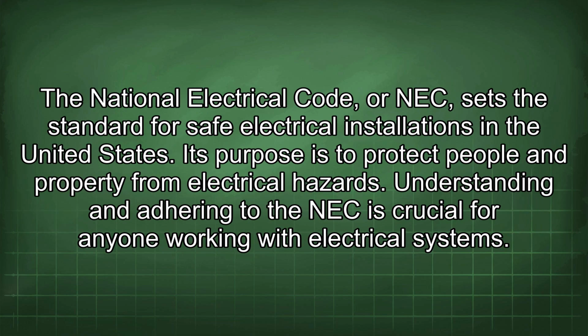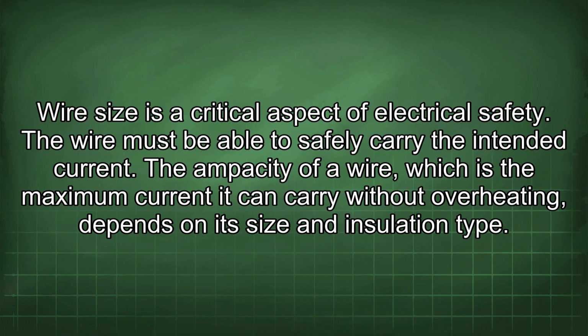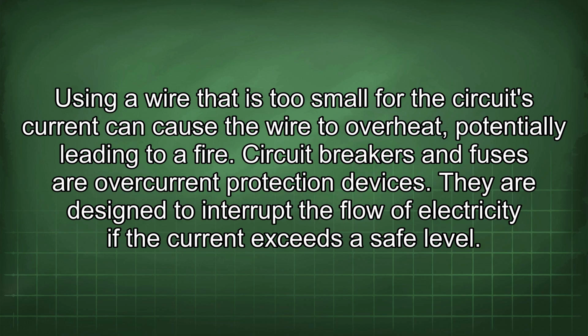The National Electrical Code, or NEC, sets the standard for safe electrical installations in the United States. Its purpose is to protect people and property from electrical hazards. Understanding and adhering to the NEC is crucial for anyone working with electrical systems. Wire size is a critical aspect of electrical safety. The wire must be able to safely carry the intended current. The ampacity of a wire, which is the maximum current it can carry without overheating, depends on its size and insulation type.